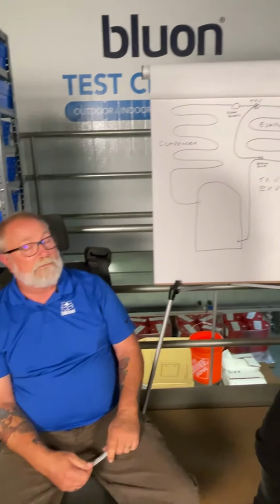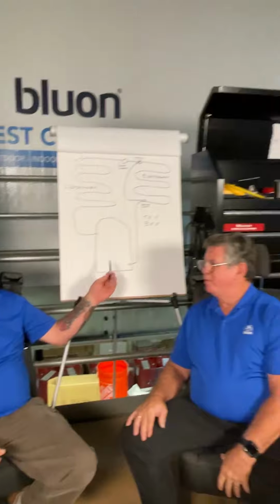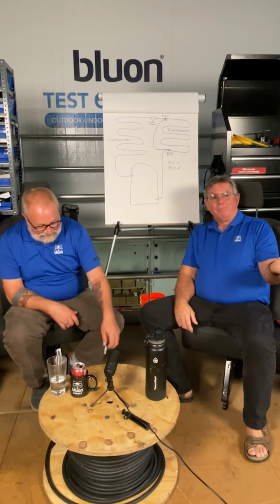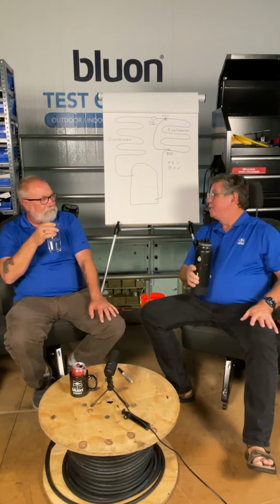Floodback. Floodback, as everybody knows in the industry, compressors do not pump liquid. At least not very long. They're designed to pump vapor. Yes, they are. If they start pumping liquid, they have a tendency to break. That's because you can't compress a liquid, but even if you just get droplets of liquid coming back, it can wash the lubrication out of your bearings. That's oil. Yep. Because that nice droplet of refrigerant just turned around and hit that warm bearing, it flashed off, and refrigerant's a great solvent. It's a great degreaser. And now you don't have oil lubricating that bearing surface, and you tear up the bearings. So the definition of floodback is liquid refrigerant entering the compressor, which it should not do. Good one, Mikey. Unless you're using liquid cooling.